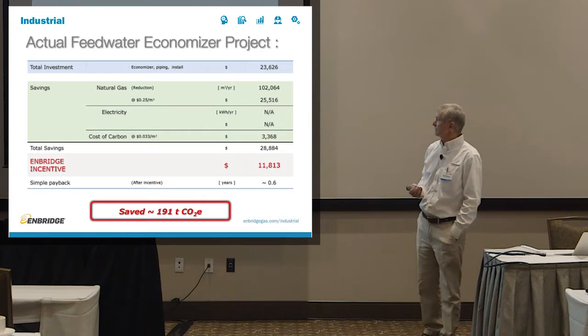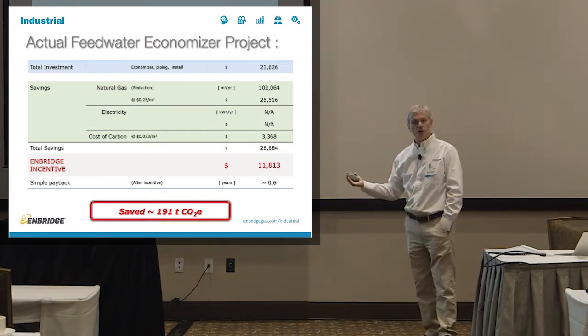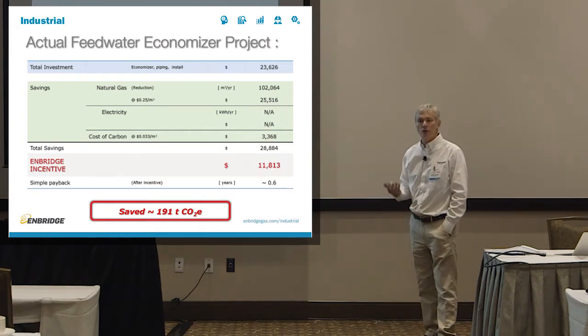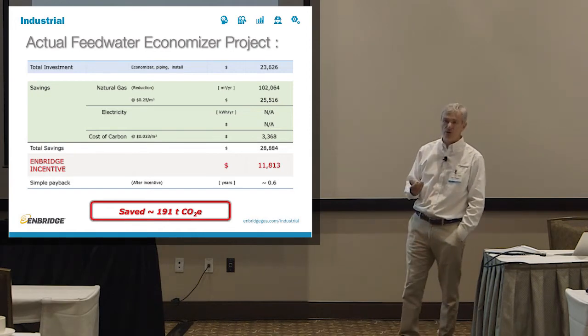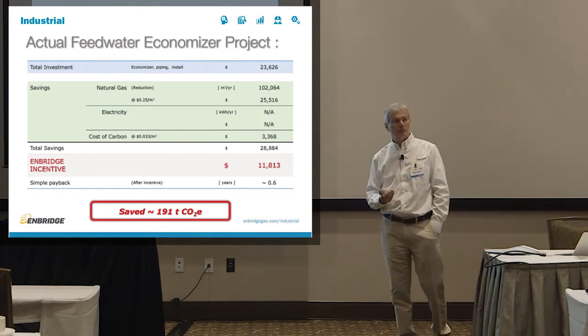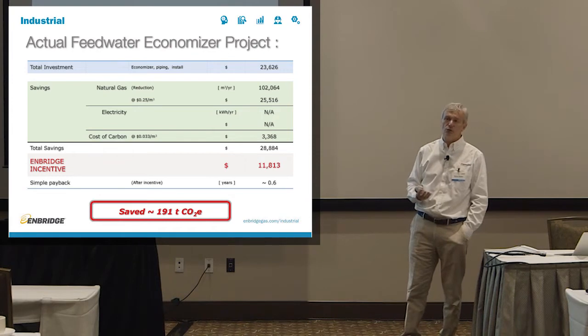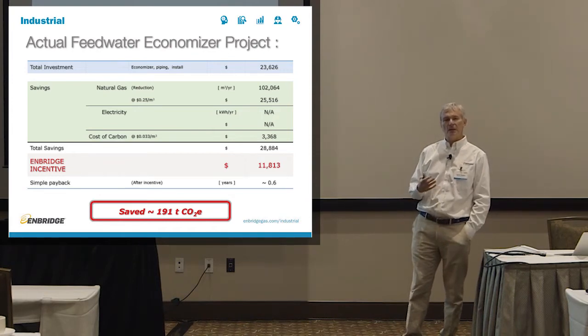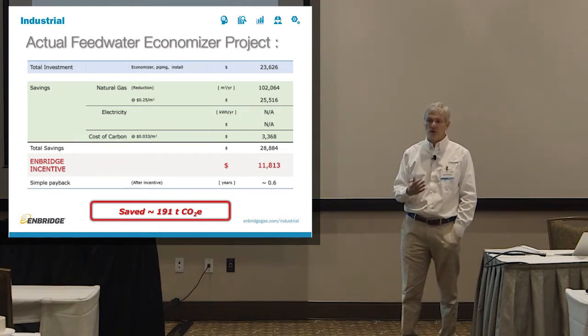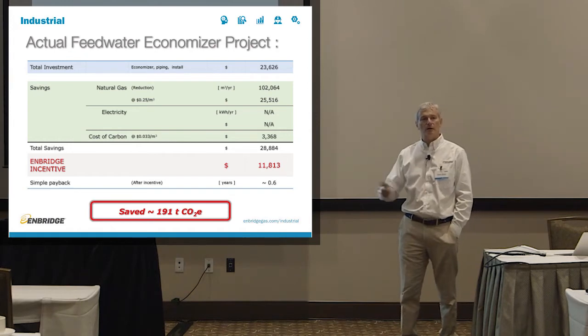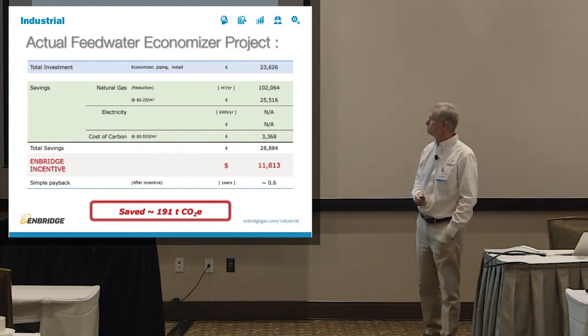So this is as simple a project as you can get in energy efficiency. If you have a steam boiler and you don't have a feed water economizer or some sort of economizer, please talk to us, because that is a very easy thing to implement. And typically people like it because it doesn't affect their process. They don't have to worry about how it affects the downstream equipment.